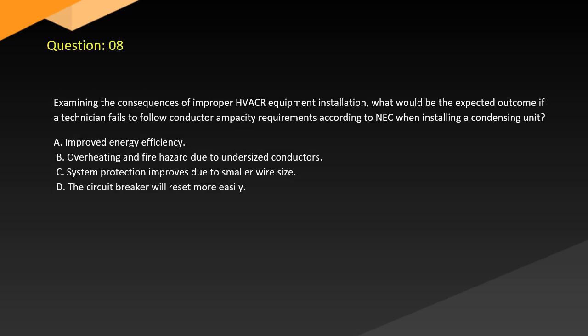Question 8. Examining the consequences of improper HVACR equipment installation, what would be the expected outcome if a technician fails to follow conductor ampacity requirements according to NEC when installing a condensing unit? A. Improved energy efficiency. B. Overheating and fire hazard due to undersized conductors. C. System protection improves due to smaller wire size. D. The circuit breaker will reset more easily.